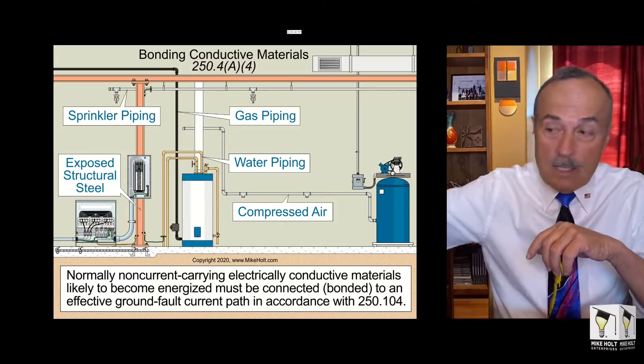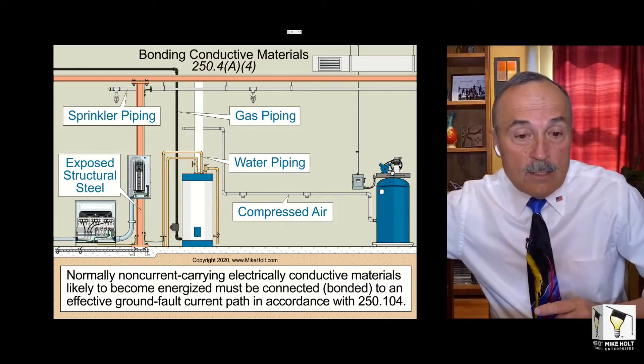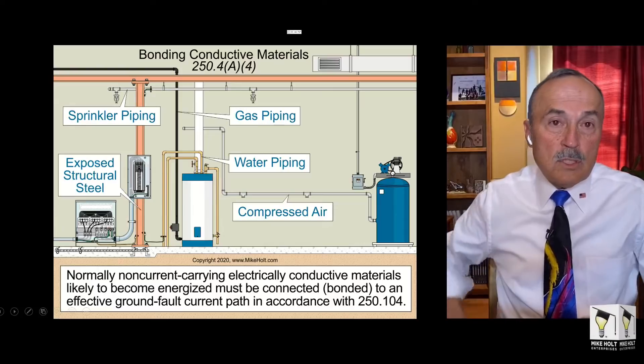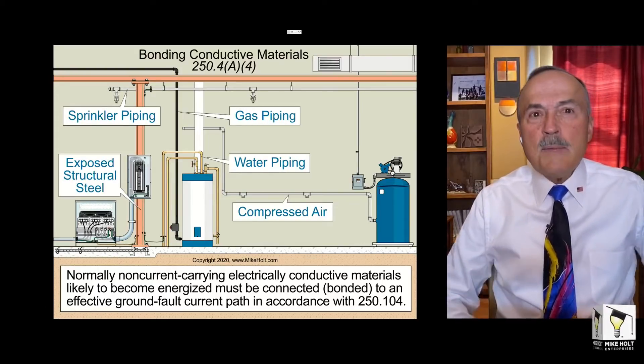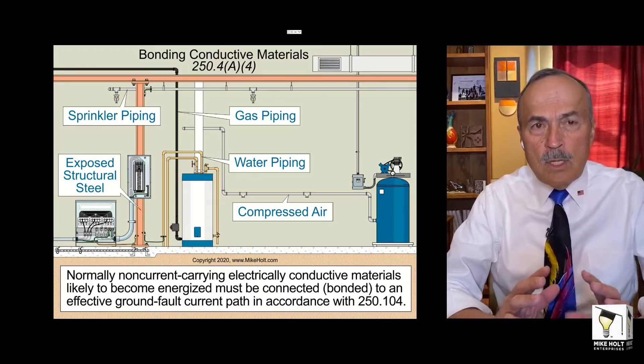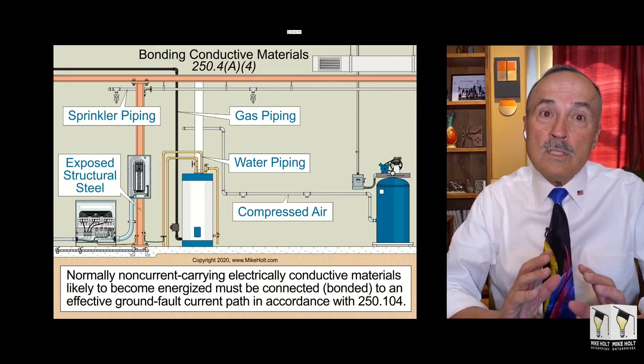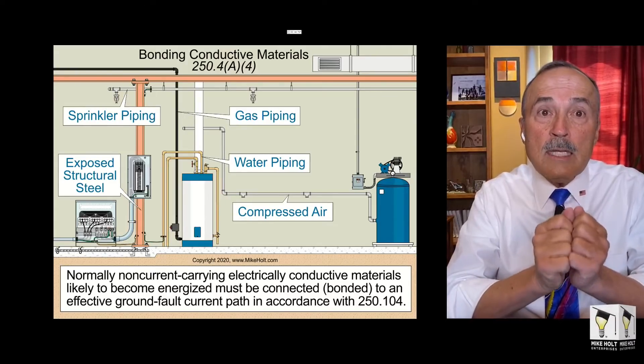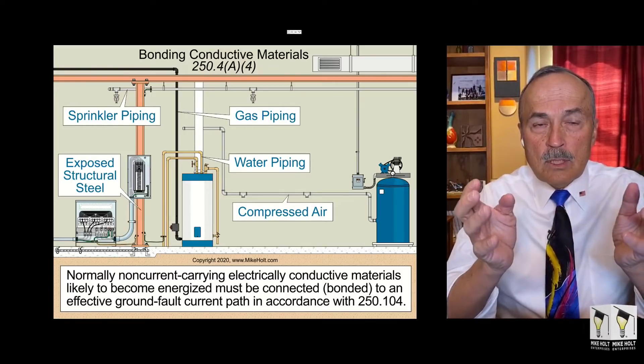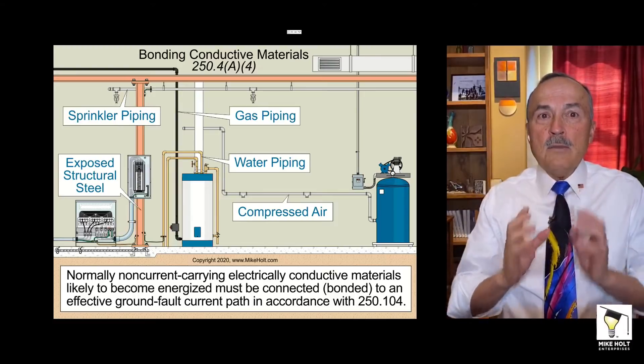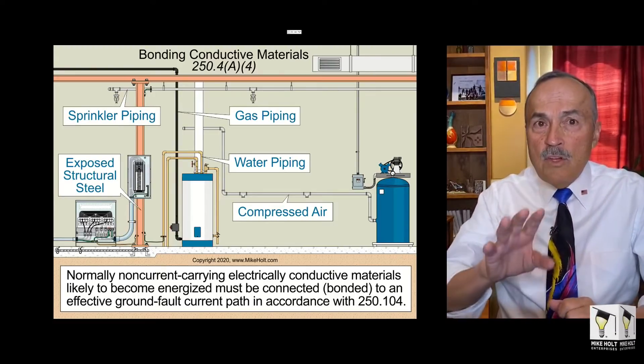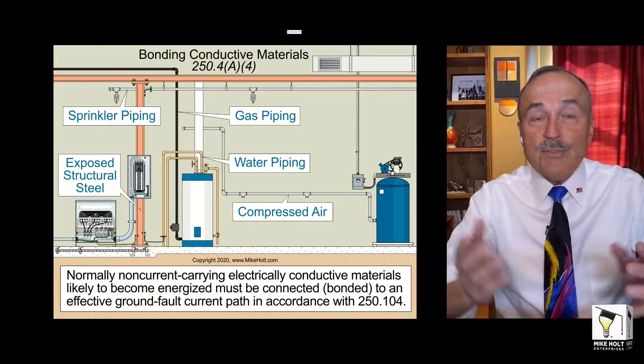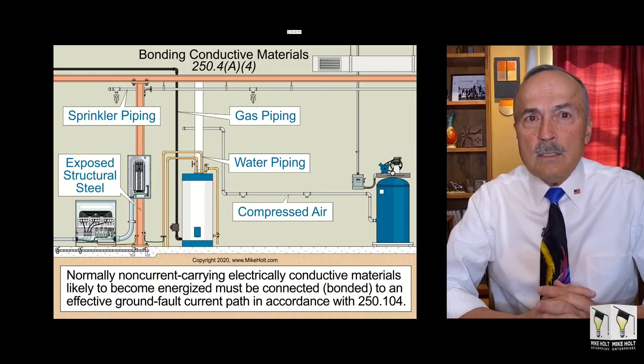NEC 250.4(A)(4) states that normally non-current-carrying electrically conductive materials likely to become energized must be addressed. According to the NFPA NEC Code Style Manual, 'likely to become energized' means there are actually conductors present. For example, if you have a box and you put electrical conductors in it and mount it on something, then whatever you mounted it on is likely to become energized — like a fence post.